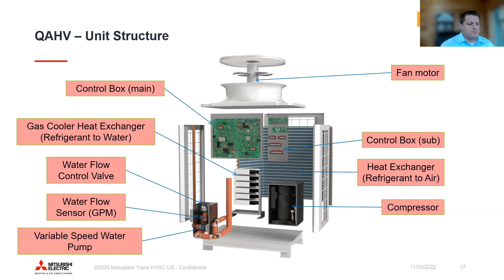And then internally, it also does have a small inverter pump and modulating discharge valve. Basically, what this means is this is what's going to control your leaving water temp. The one difference between this and maybe VRF is that while it's an inverter compressor, most of the time it's going to run at 100%. So it really uses the inverter more for soft start purposes and efficiency purposes of the motor. In general, the compressor is going to run at that highest frequency, and the water pump is going to dictate your actual leaving water to the tanks and secondary heat exchanger.